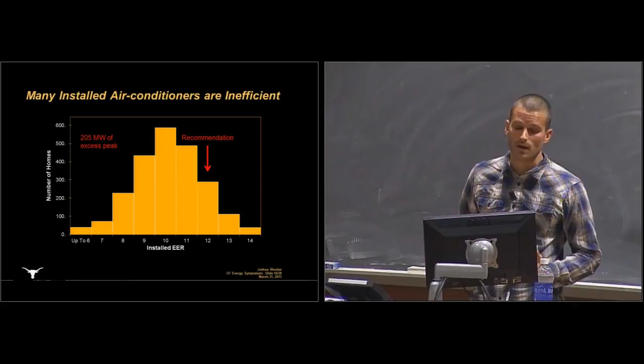Here's a histogram of air conditioners that are actually installed, taken from the nameplate, and this is what Austin Energy recommends: an energy efficiency ratio of 12. So everything to the left of that is responsible for about 205 megawatts of excess peak.